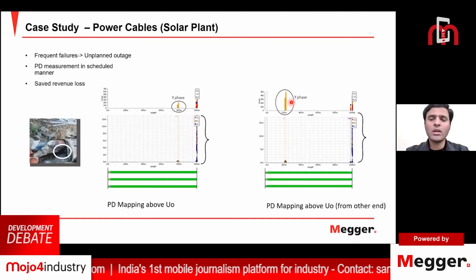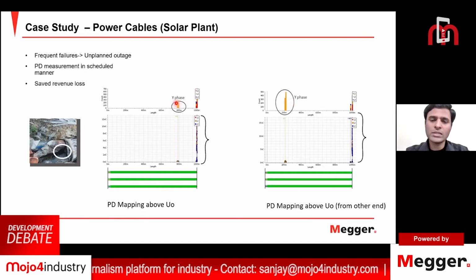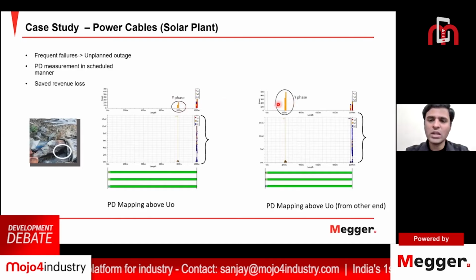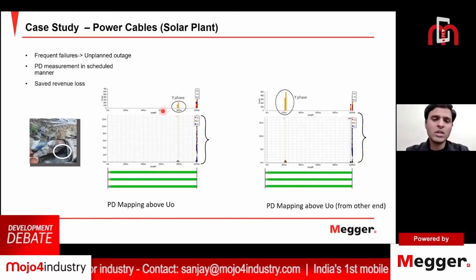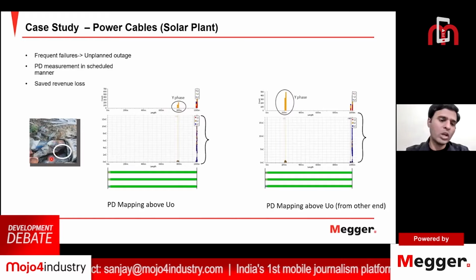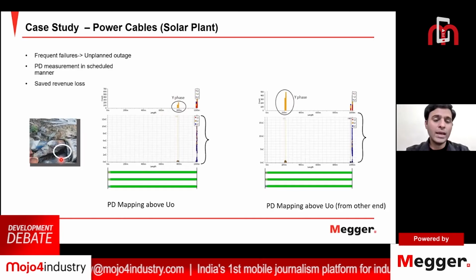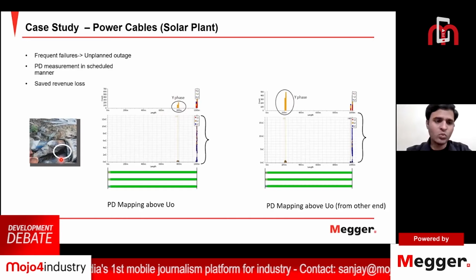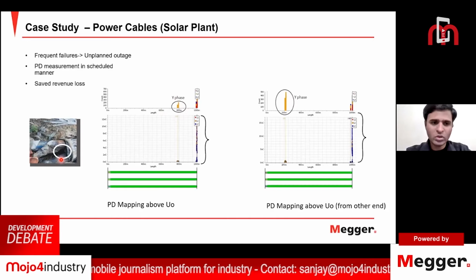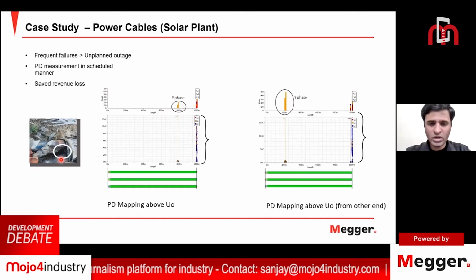And the utility decided to do an excavation at that spot, 800 meters from the first test end and 200 meters from the other end. The same location was excavated and a joint was found with white patches, which was deteriorated. By doing a planned shutdown, as it's a solar power plant, they have a shutdown at night time, and the testing was done at night. They could avoid a major failure which could have occurred in the service period.